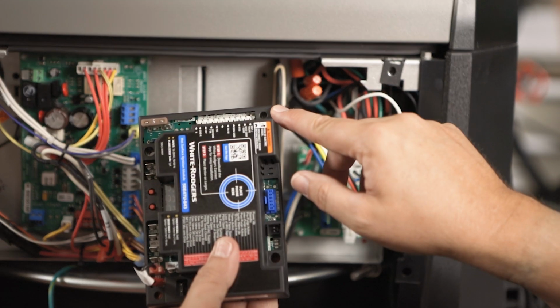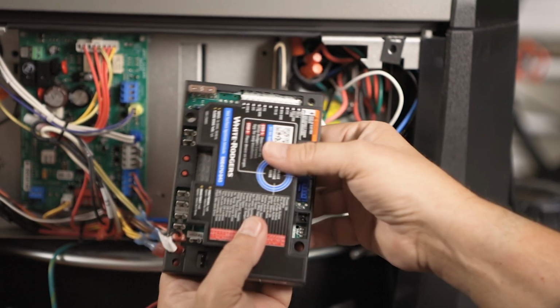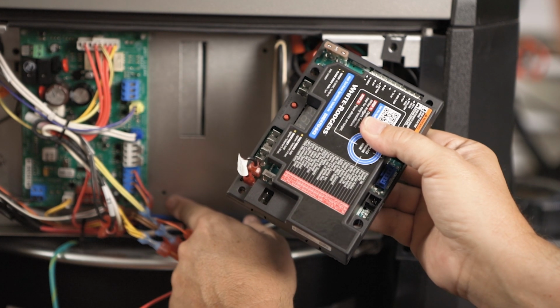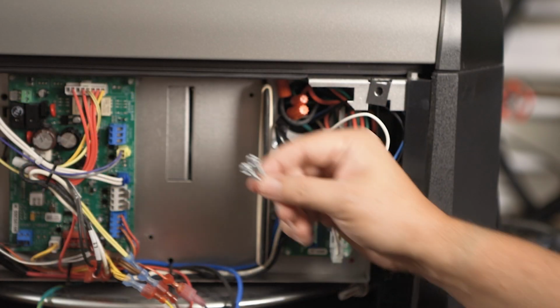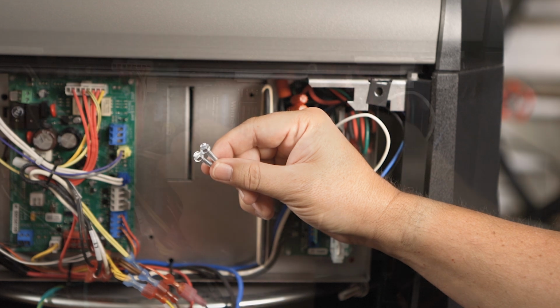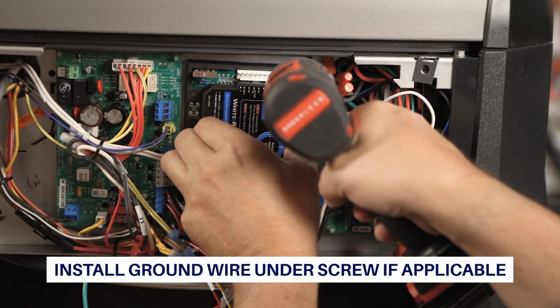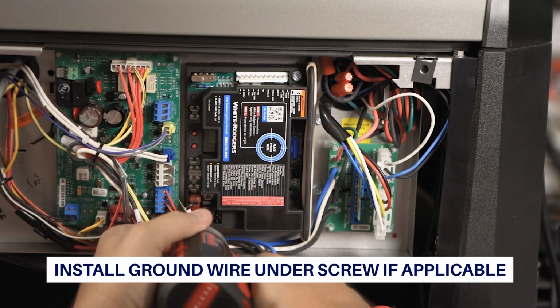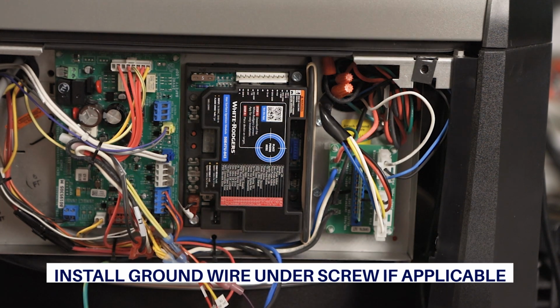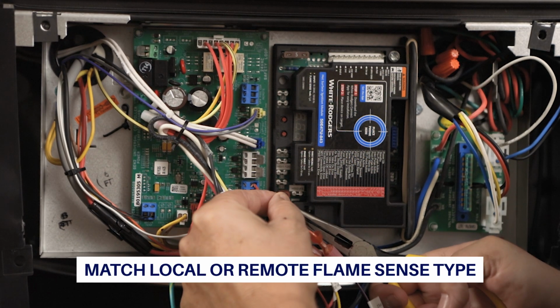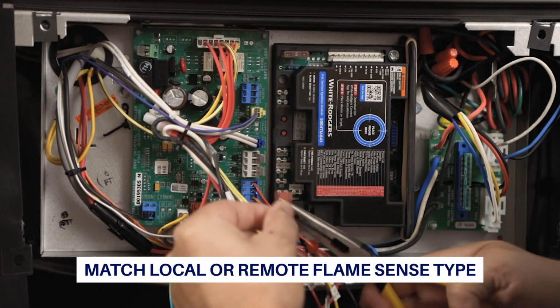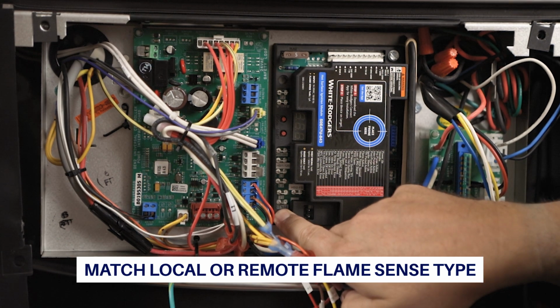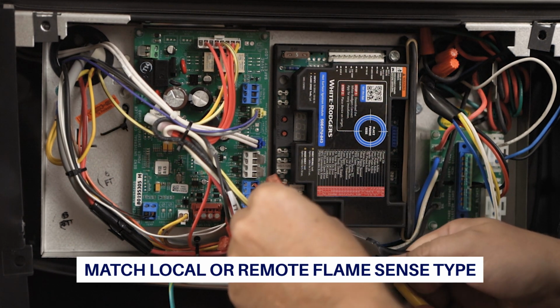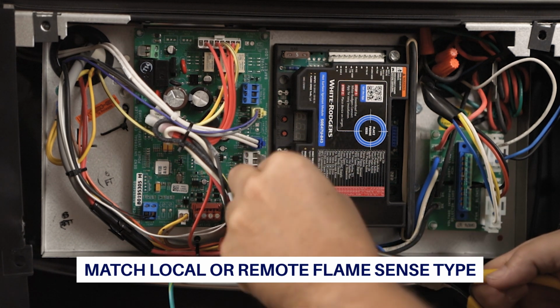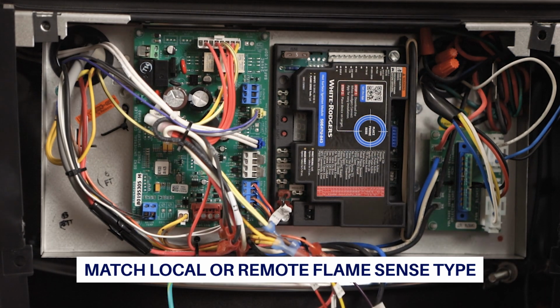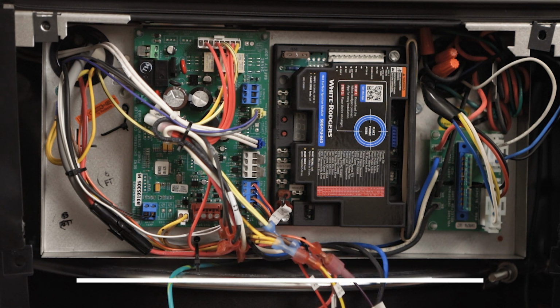Mount the 50E47U-843 in the unit using the mounting holes used by the existing control if possible. Longer screws are supplied in the accessory bag if needed. Be sure not to damage any components such as transformers, wire harnesses, or blower wheels when drilling or installing screws. In applications using a remote flame sensor, remove the flame sense jumper and plug the flame sense wire into the Sense terminal. For this application, the flame sense is detected through the hot surface ignition module, so the local flame sense jumper wire is to be left on the control.